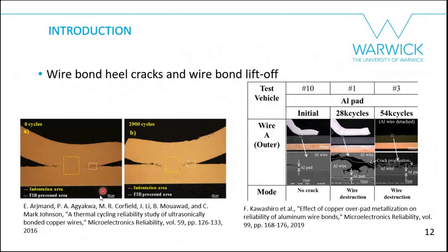There are open-access papers showing these failure mechanisms. Cracks start at the attach point of the wire bond to the chip or DBC copper substrate, and as the number of cycles increases you can see how initially there is a good attachment but cracks develop, eventually reaching the point called wire bond lift-off where the aluminum wire is just barely touching.